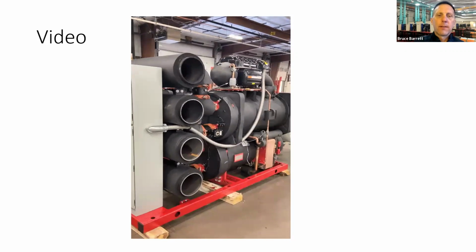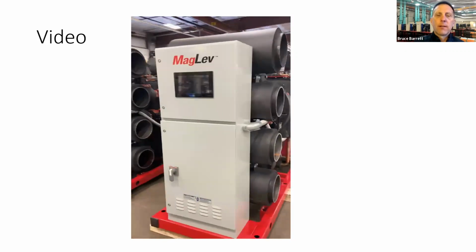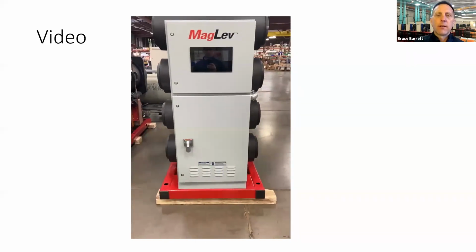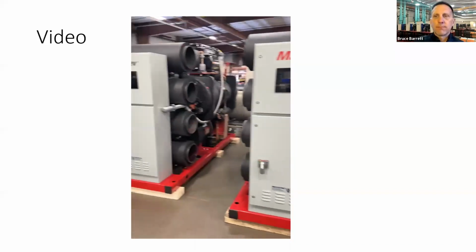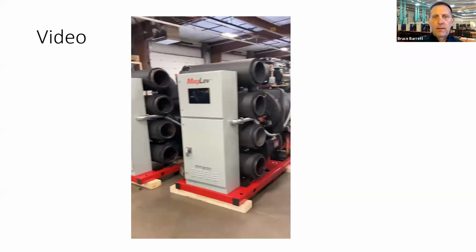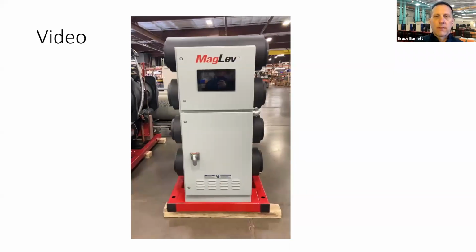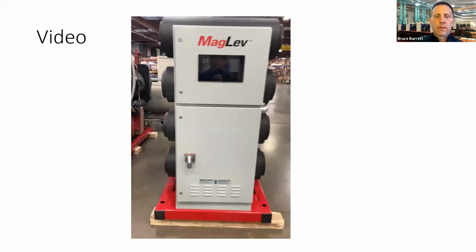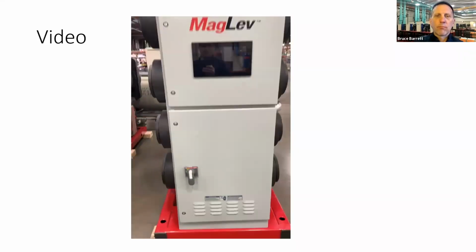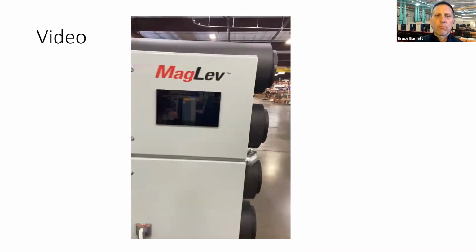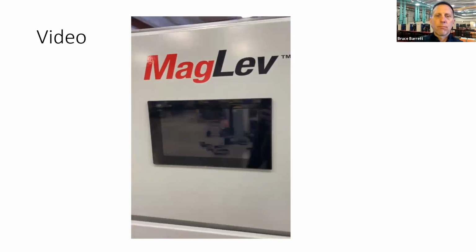water-cooled chiller. All right. One of the great features of this machine is it's less than 36 inches wide. You can get it through a 3.0 door. You can stack multiple machines together in a very small space and build a chiller well over 1,000 tons. Some of the great features: electrical isolation on each module to kill power there. Our unit subcontrollers that can be tied to the master.